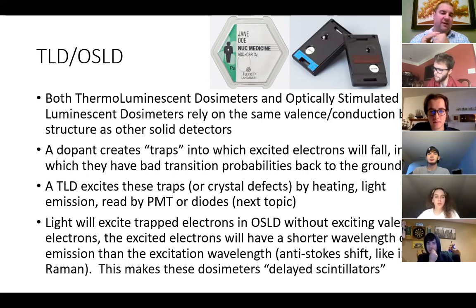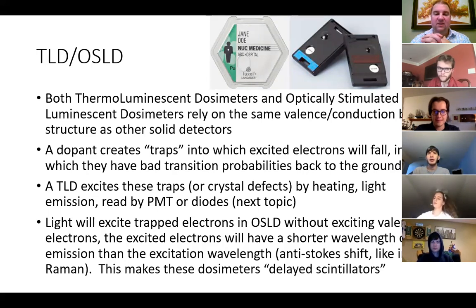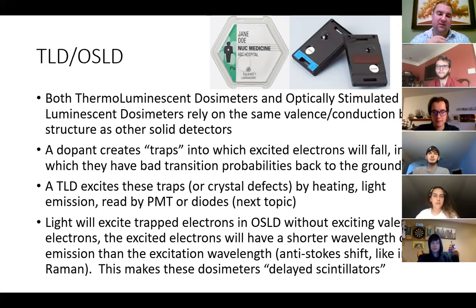We have both thermoluminescent dosimeters (TLDs) and optically stimulated luminescent dosimeters (OSLDs). TLDs are the ones in those black plastic cases — traditionally used at Brookhaven National Lab. OSLDs are more typically seen in hospitals and academic settings. Both rely on the same valence and conduction band structure, but the dopants work differently in that they actually trap the excited electrons.